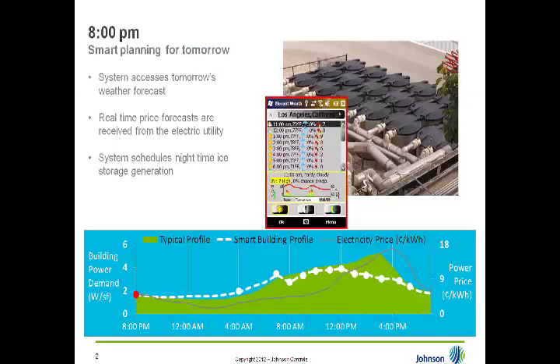This story actually starts at 8 o'clock the night before. The smart building systems go out and look at the weather forecast for the next day. They have a detailed dynamic predictive model of the energy use of the building. Based on the next day's weather, which is expected to be both hot and humid, the system forecasts exactly how much ice needs to be produced to be melted the next day to reduce electrical demand. This building is also subject to real-time pricing, so a forecast of that pricing schedule for the next day is made as well. The system starts making ice as soon as the building goes into off-peak periods when the price is low.